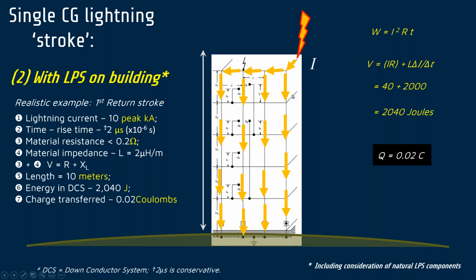In this example, the existing lines illustrate down conductors where the arrows are going down, with horizontal bonded conductors going around the building. Looking at the overall configuration, it's effectively a matrix of conductors parallel with each other around the building, allowing multiple paths for the current to flow to ground. On the other side, the closer these conductors are to each other, the lower the electric fields will be that build up between the electrodes.